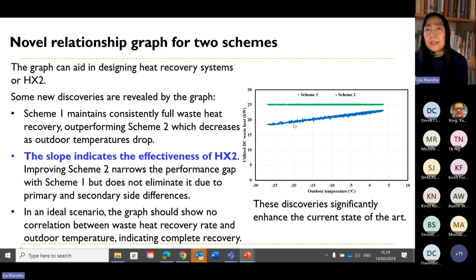In scheme two, the waste heat recovery decreases as outdoor temperature drops. Second, this is very interesting because we discovered that the slope of the line actually represents the effectiveness of the heat exchanger, with the optimal slope being 0 degrees, as in the horizontal line of scheme one. Improving the effectiveness of the heat exchanger in scheme two, for example by lifting this blue line up, can narrow the performance gap between scheme one and scheme two, but the gap can never be eliminated due to the connection differences.